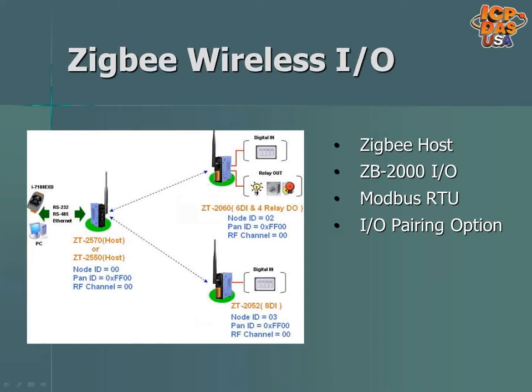ZigBee wireless I/O modules can communicate wirelessly over Modbus RTU protocol. The host converter can be connected to a PC or controller like our touchscreen PLCs, UPAC embedded controllers, or PAC controllers. The program on the PC or controller can communicate with the ZigBee I/O modules as if they were directly connected. With the I/O pairing option, no host converter is needed, so the input on one can trigger the output on another in a stand-alone application.